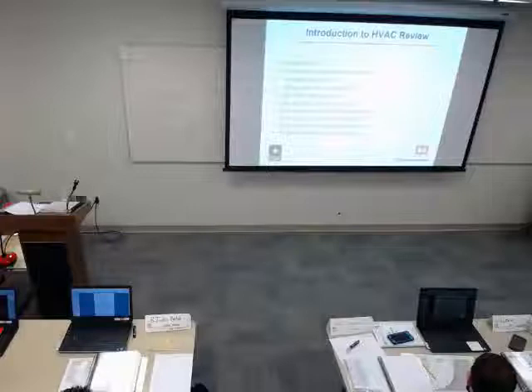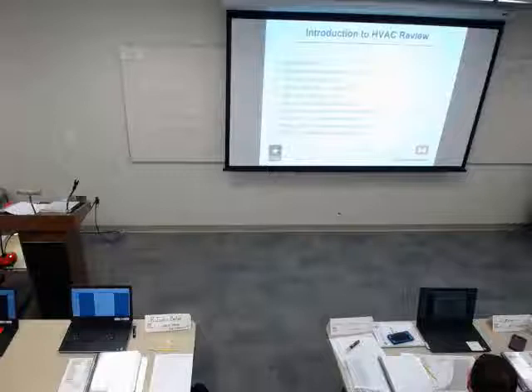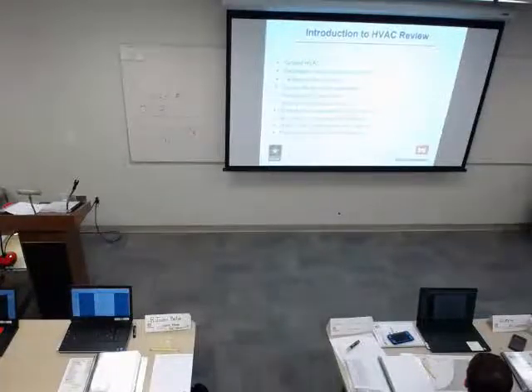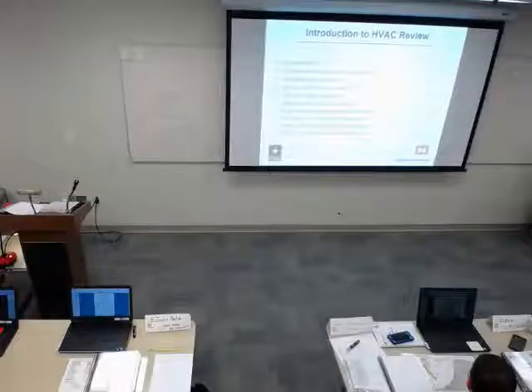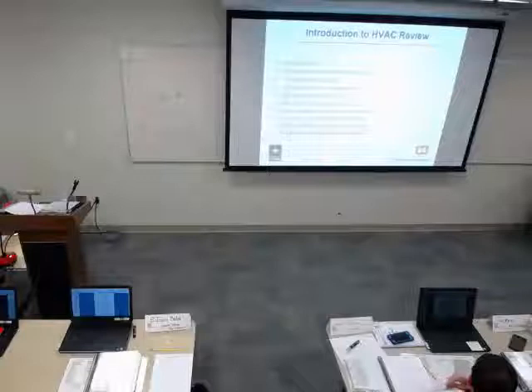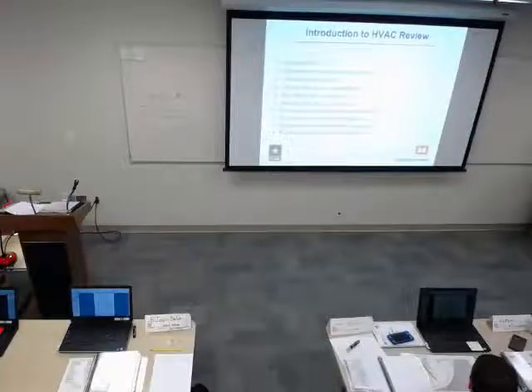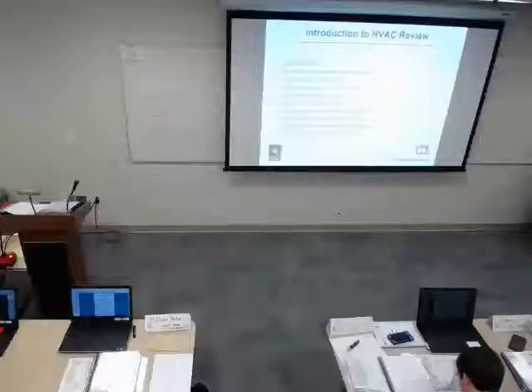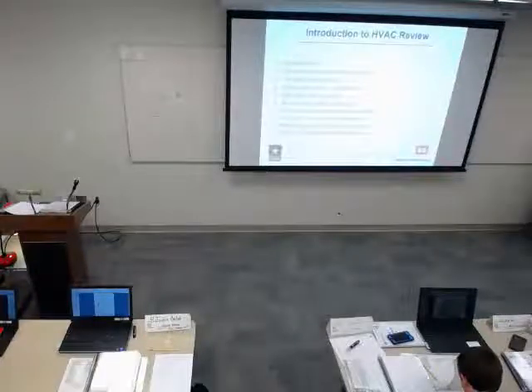That really can't be overemphasized. We have a fire station, a brand new one. The architect meant well, but he didn't know that air goes through that insulation. So the area above the ceiling had bad insulation, and the air was coming down into the wall and actually hit the ceiling too. During the winter, the ceiling and the walls would get down to the mid-40s. We were getting complaints about fire guys who couldn't get to sleep at night. They were putting on gobs of blankets. I'm talking gobs. And still couldn't sleep.